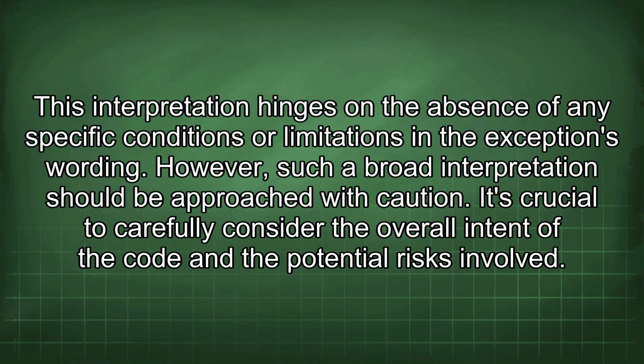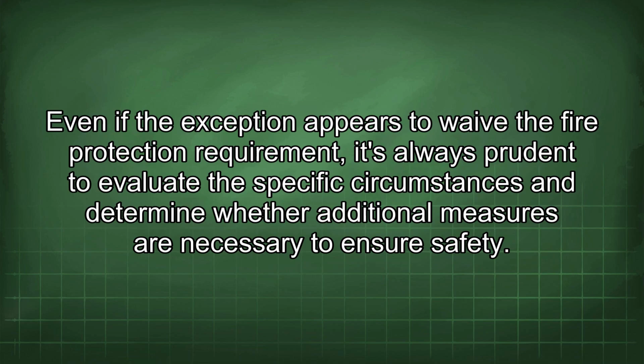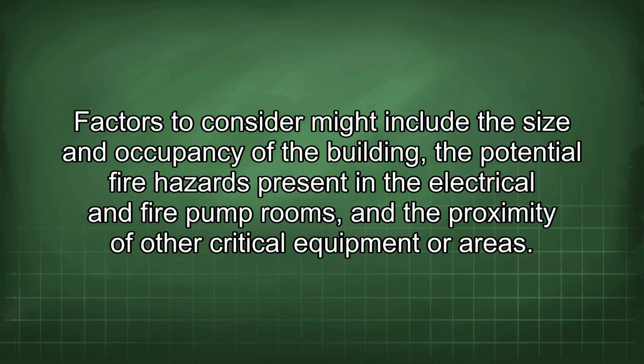However, such a broad interpretation should be approached with caution. It's crucial to carefully consider the overall intent of the code and the potential risks involved. Even if the exception appears to waive the fire protection requirement, it's always prudent to evaluate the specific circumstances and determine whether additional measures are necessary to ensure safety. Factors to consider might include the size and occupancy of the building, the potential fire hazards present in the electrical and fire pump rooms, and the proximity of other critical equipment or areas.